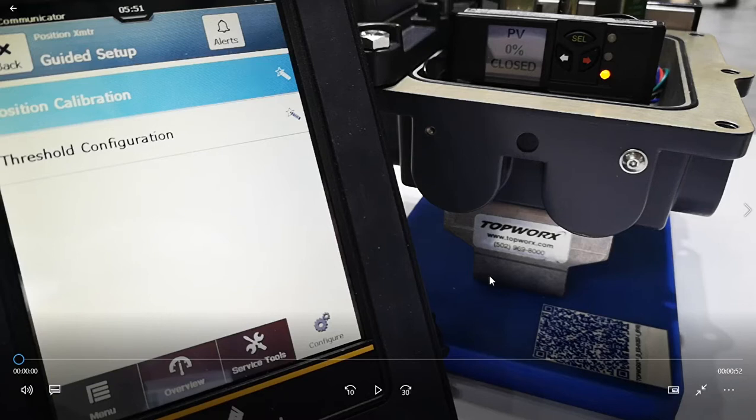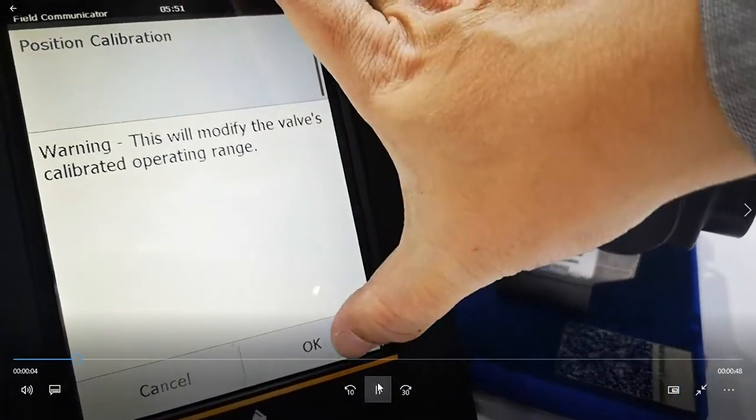Hi, my name is Mike Hulls from Emerson working with TopWorx. Today we're going to see how the HART 7 device from TopWorx interfaces very nicely with an AMS Trex. What we're doing today is calibrating, and although you can do this directly on the device with the digital display, in this video I'll be showing how you can calibrate using an AMS Trex. You can see now we're clicking on position calibration.